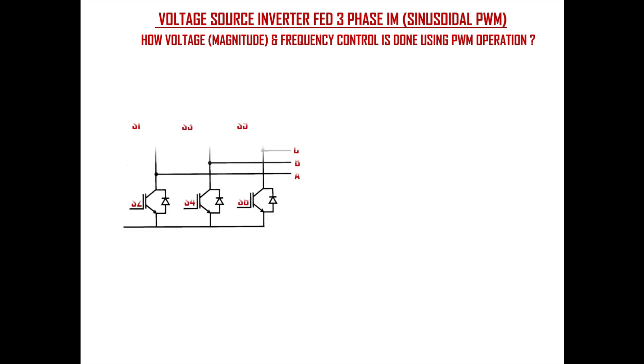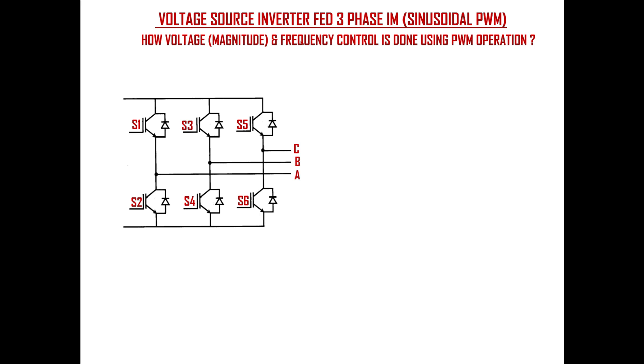First, let's consider a three-phase voltage source inverter consisting of six IGBT switches as shown here, which will be connected to a three-phase induction motor. For simplicity I have not shown the induction motor here. The inverter can also be made up of six thyristor switches, but keep in mind that if you are using thyristor switches then you need to have a separate commutation circuit to turn off the thyristors — that is, to reverse bias the thyristors.